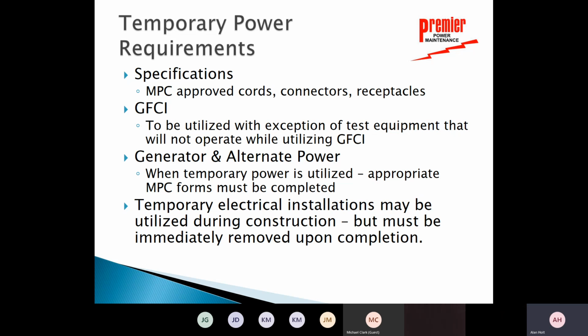On top of that, you need to be aware that we can't use what we typically use for cords, connectors, and receptacles. They have to be GFCI protected. Here's the exception, with certain test equipment that will not operate with GFCI protection. That really doesn't impact us anymore.